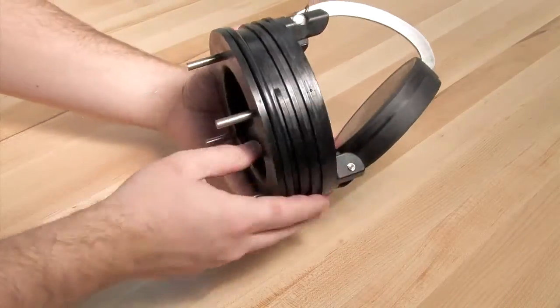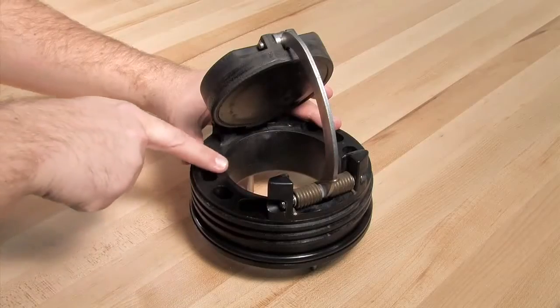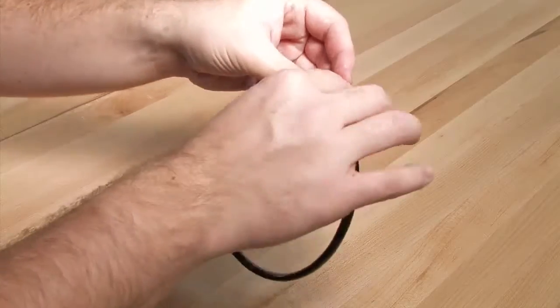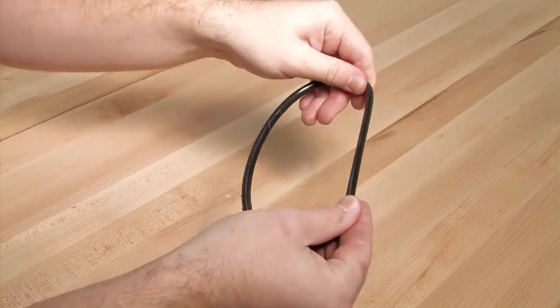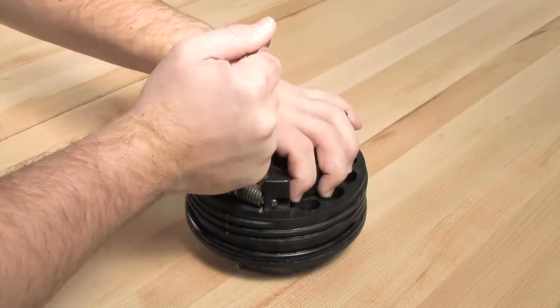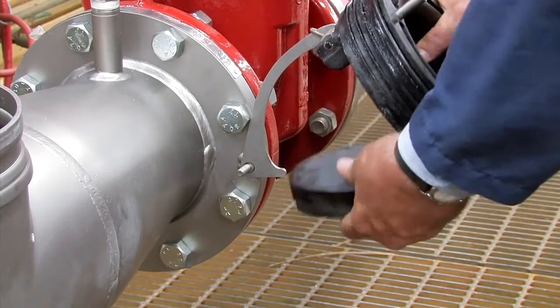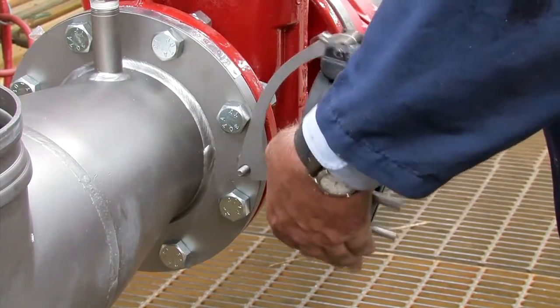Inspect all check components including the check body, clapper, seat, and o-ring for nicks, cuts, or debris. Take appropriate action to clean or replace any damaged parts. The two and a half to four inch checks should be closed by hand, while the six inch checks should be closed with the help of the opening strap found on the outlet flange.